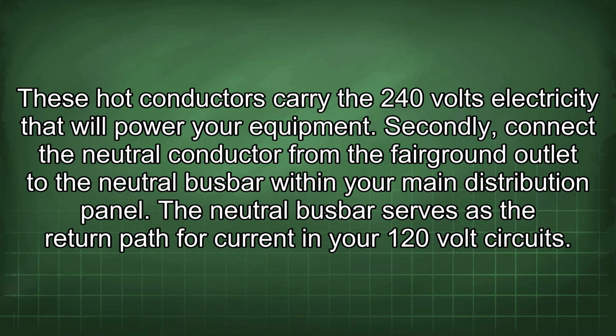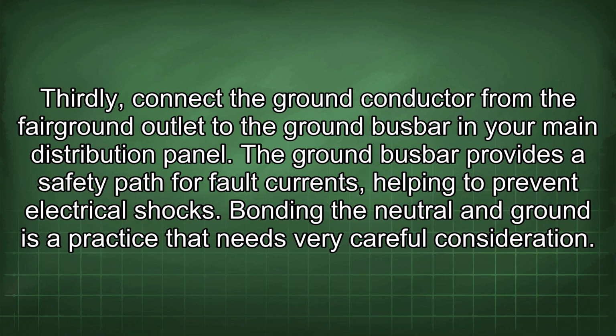Secondly, connect the neutral conductor from the Fairground outlet to the neutral busbar within your main distribution panel. The neutral busbar serves as the return path for current in your 120-volt circuits. Thirdly, connect the ground conductor from the Fairground outlet to the ground busbar in your main distribution panel. The ground busbar provides a safety path for fault currents, helping to prevent electrical shocks.